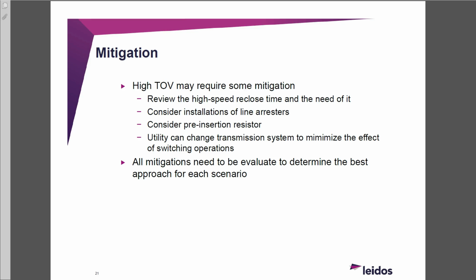And again, any choice that you pick, revise it with EMTP. If you pick an arrester or whatever, redo the work, test to make sure, and emphasize the high-speed reclose. If you're thinking about changing the high-speed reclose, you've got to do a PSS/E or PSLF study to make sure that your system is not going to be adversely impacted. So if you have this issue, you better buy EMTP before January, because you need to do this study.